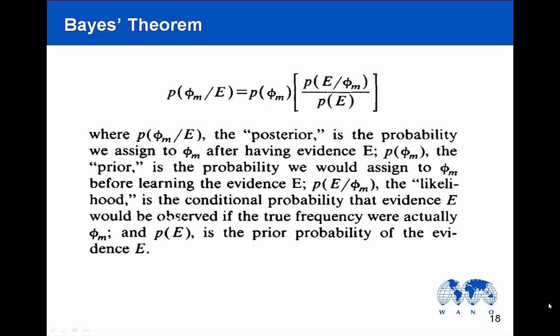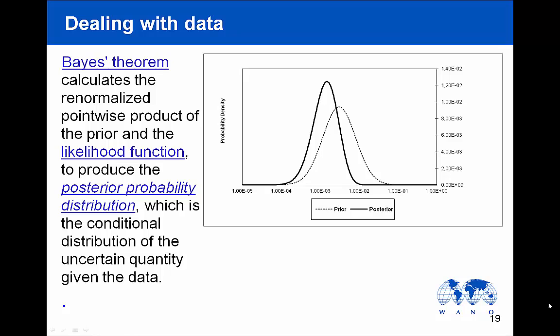Usually we have few sources of data. Those are events that happened on our plant, on different plants of the same design, and even in different industries. But how to combine these types of information? Bayes' theorem serves this purpose. Let's look at an example. For instance, we have general failure rates, and we should adapt them for our case, for an NPP or unit. Here, Bayes' theorem is employed for updating generic data.